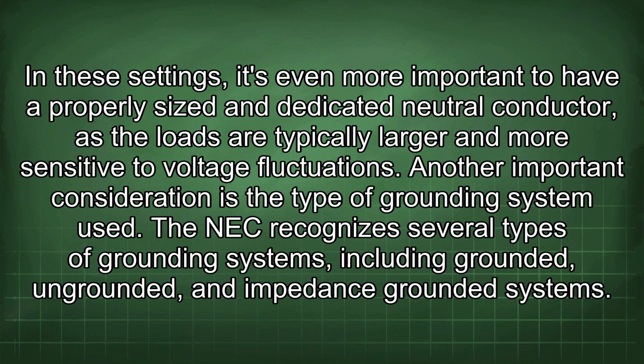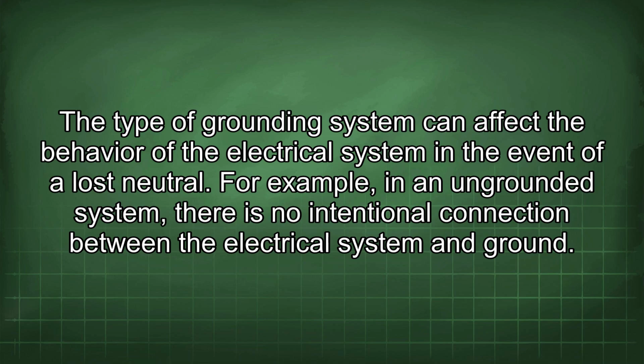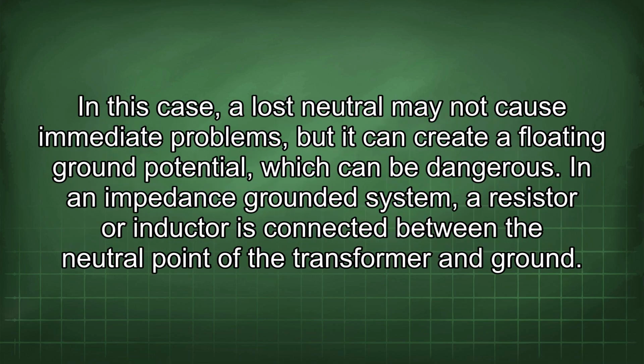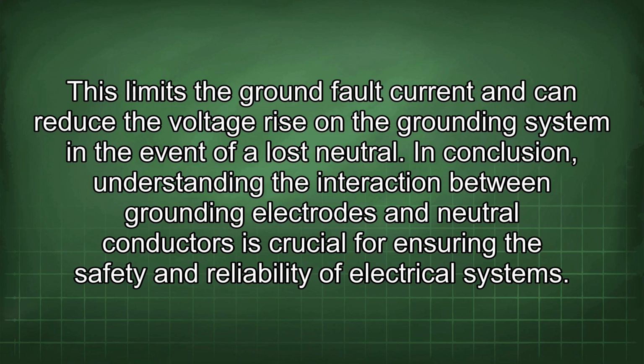Another important consideration is the type of grounding system used. The NEC recognizes several types of grounding systems, including grounded, ungrounded, and impedance-grounded systems. The type of grounding system can affect the behavior of the electrical system in the event of a lost neutral. For example, in an ungrounded system, there is no intentional connection between the electrical system and ground. In this case, a lost neutral may not cause immediate problems, but it can create a floating ground potential, which can be dangerous. In an impedance-grounded system, a resistor or inductor is connected between the neutral point of the transformer and ground. This limits the ground fault current and can reduce the voltage rise in the grounding system in the event of a lost neutral.